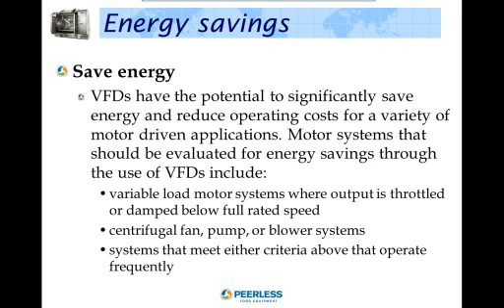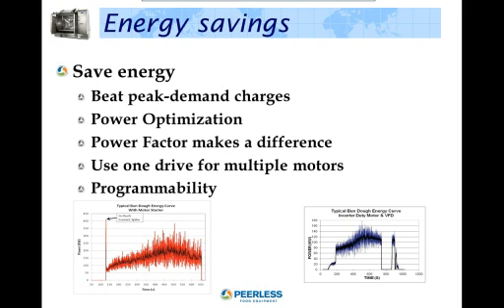Beat peak demand charges. VFDs also affect peak demand electricity prices that the utility charges to companies that exceed preset limits, such as when industrial motors are started across the line, they draw large peaks of current. VFDs help reduce these peaks by supplying the power needed by the specific application and gradually ramping the motor up to speed to reduce the current draw.